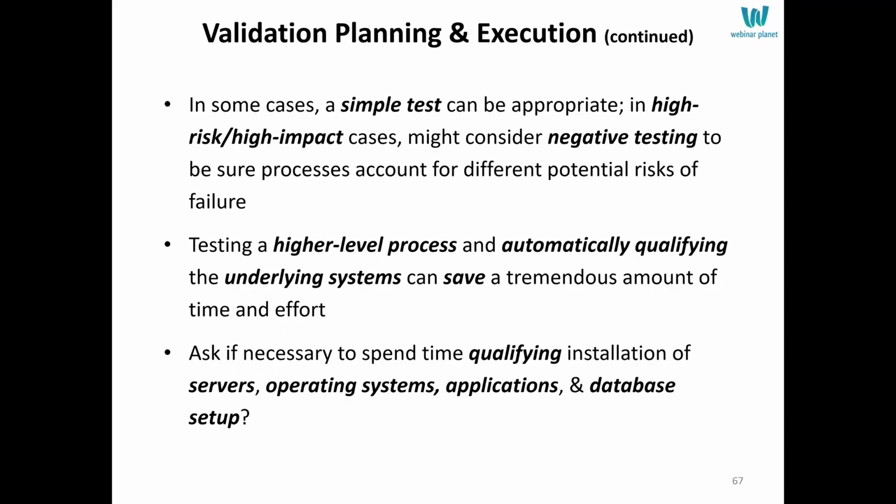So based on that, in some cases, a test might be simple if the requirement doesn't have a high potential risk if it fails to be met. But if a requirement does have a high potential risk if it fails to be met, you do more rigorous testing. You might include, in addition to positive test scenarios, which show that the system does what it purports to do, negative testing scenarios, which show that the system doesn't do what it doesn't purport to do. You might do boundary or stress testing. You might have multiple rounds of testing. Whatever it takes, you would do it based on whatever rating came up for risk.